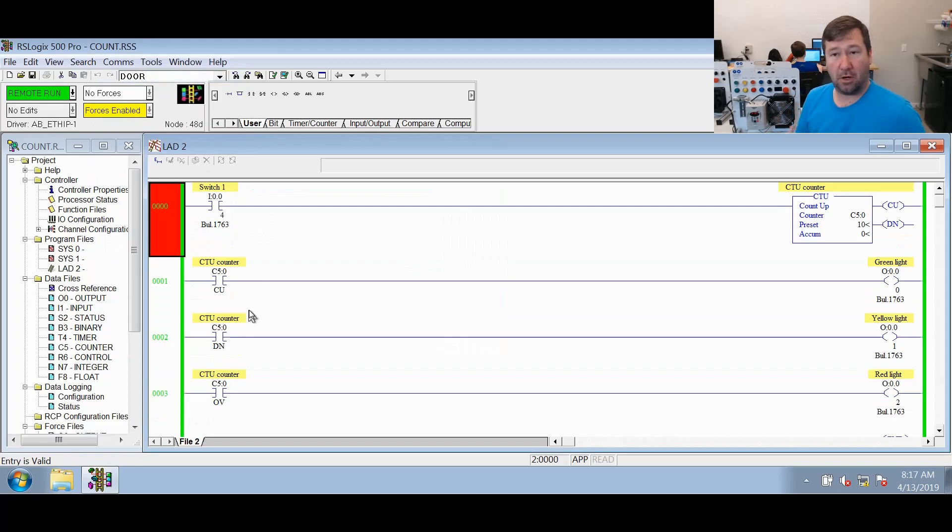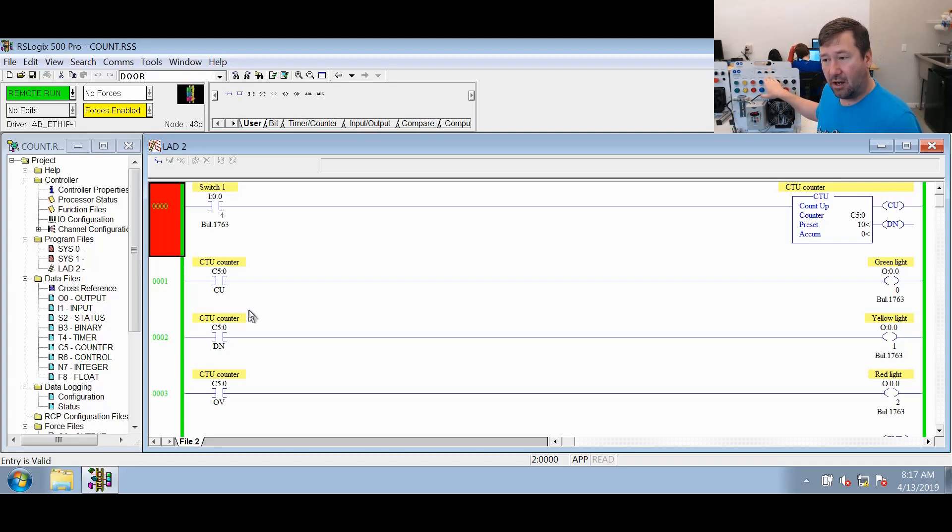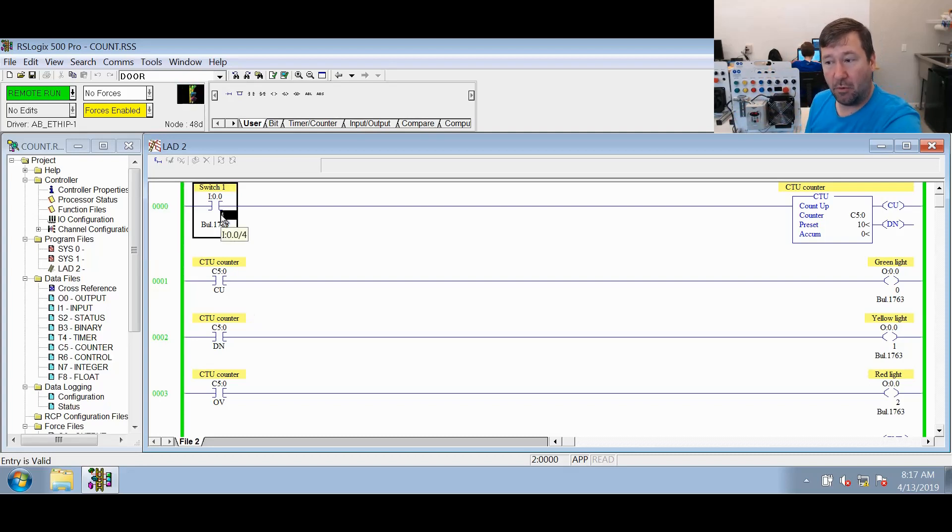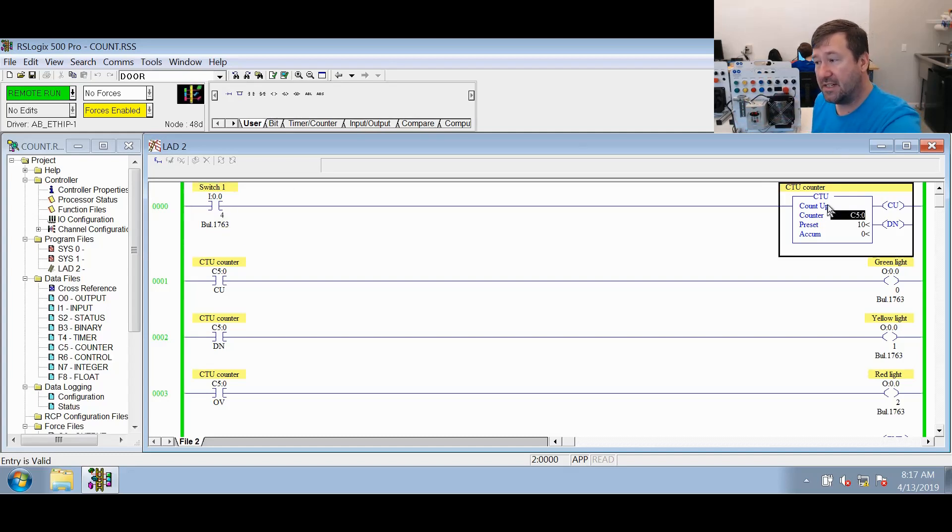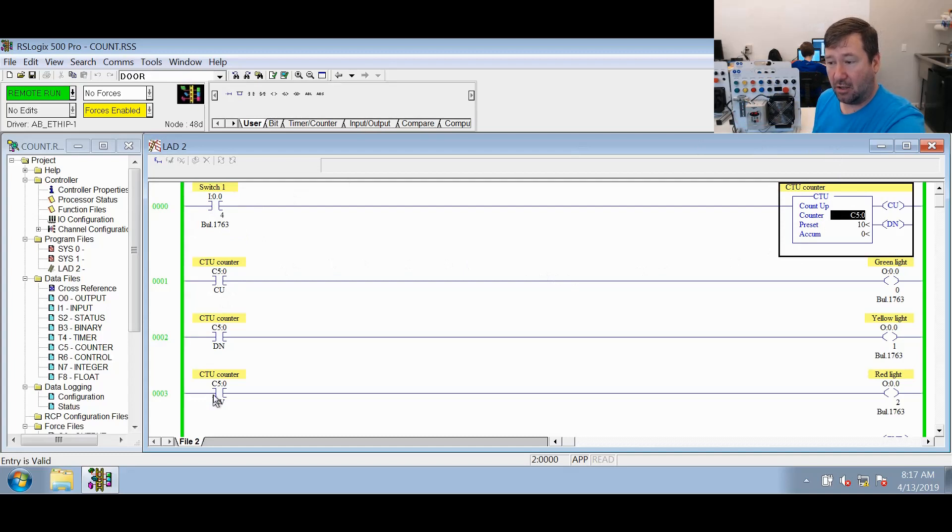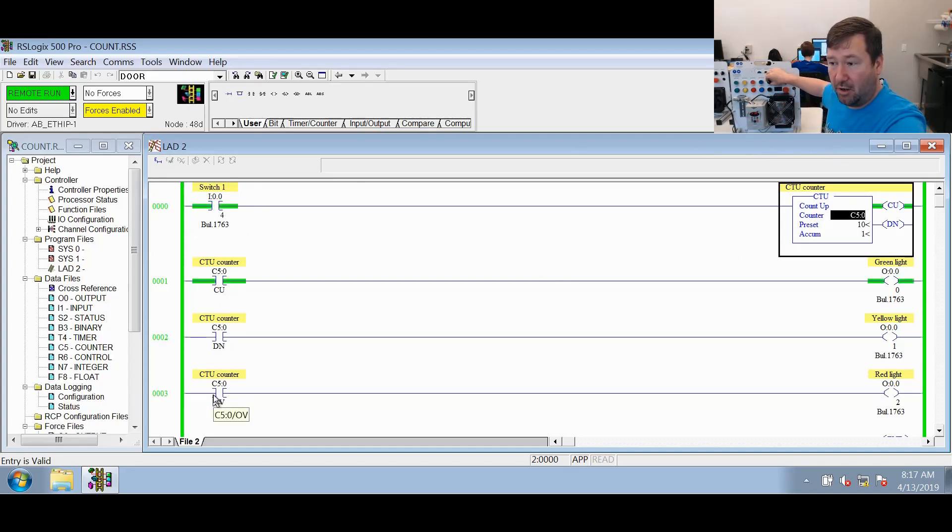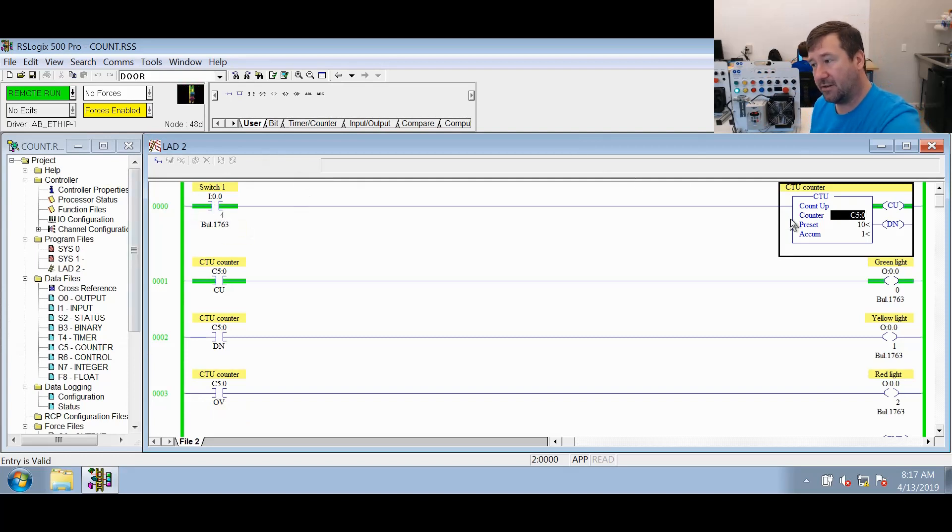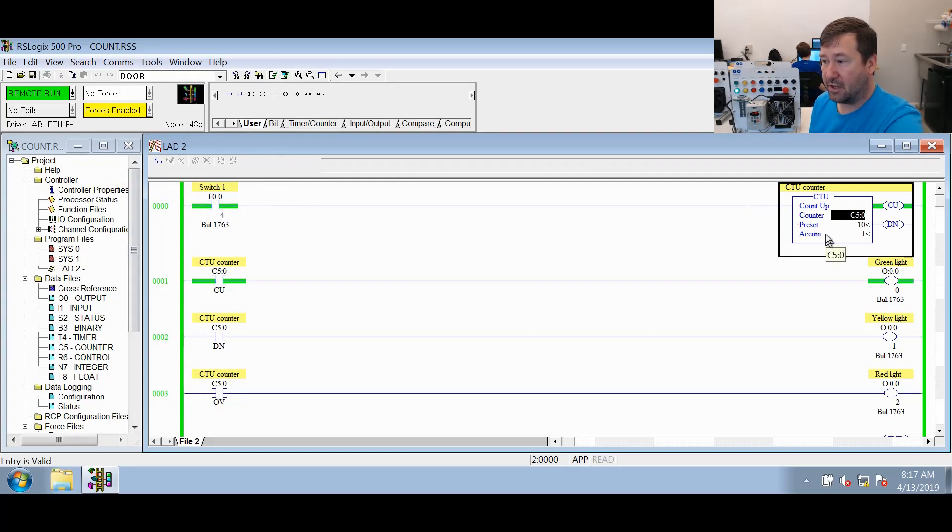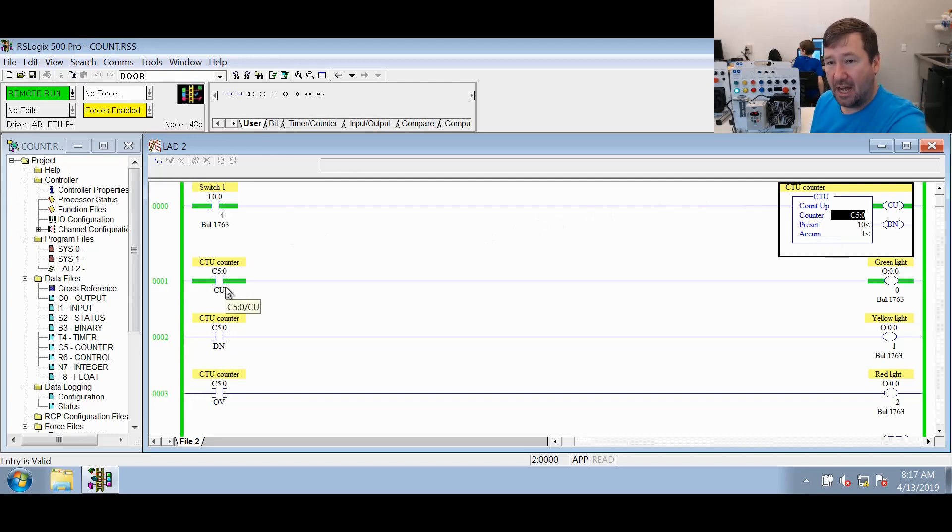So we're online and our processor is running, and we can see right now switch one is off. So this XIC is going looking for a one. It sees a zero, so it's false. So our CTU is false. And you can see all our bits right now are zero. So we switch switch one on. Now this says go look for a one. It sees a one, so it's true. So our counter now is true. We can see our accumulated went up to a value of one, and our CU bit is now a one.